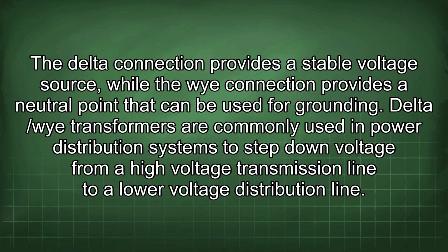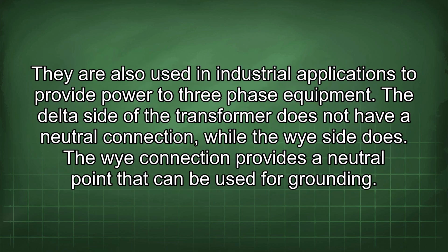Delta/Y transformers are commonly used in power distribution systems to step down voltage from a high voltage transmission line to a low voltage distribution line. They are also used in industrial applications to provide power to three-phase equipment. The delta side of the transformer does not have a neutral connection, while the Y side does. The Y connection provides a neutral point that can be used for grounding.